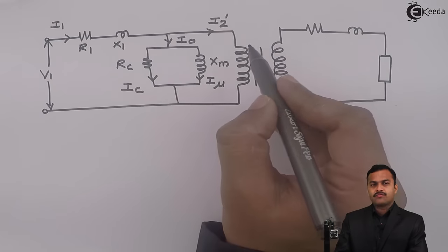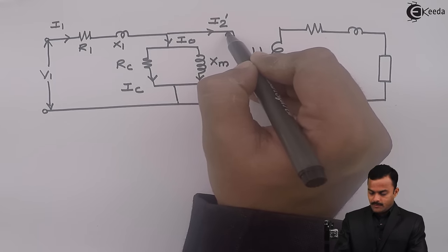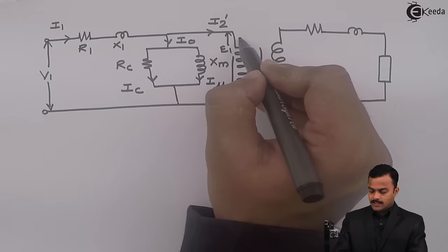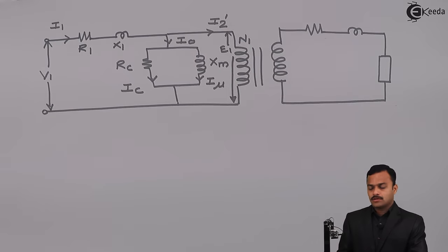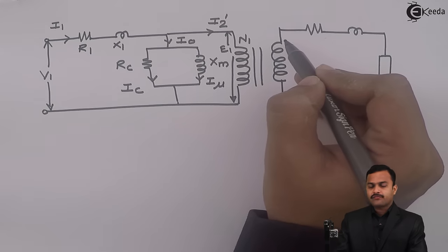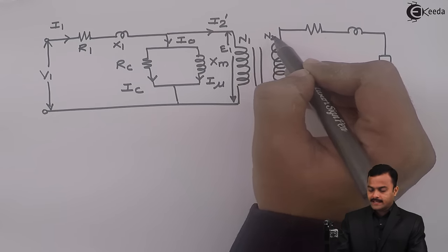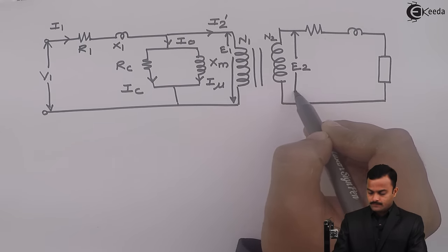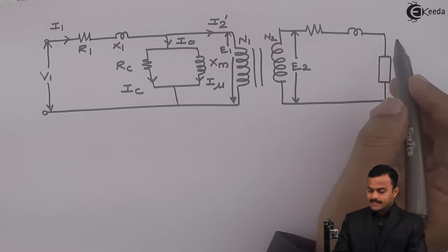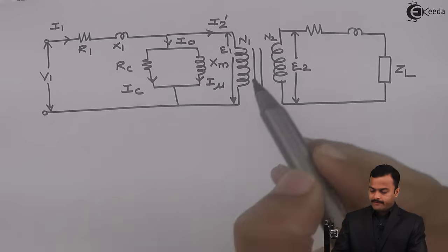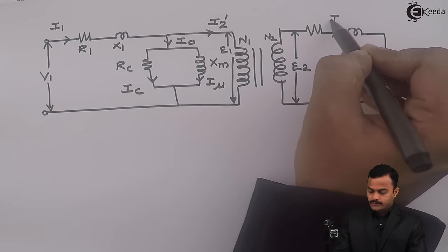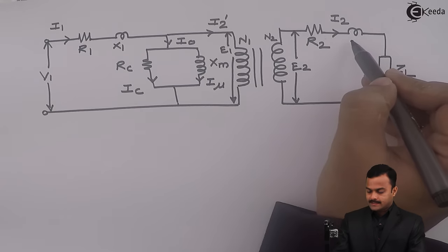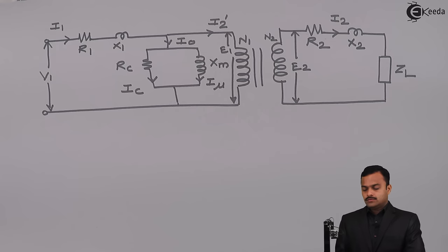Because of flux phi, there will be an EMF induced at the primary side, represented as E1, and that depends upon the number of turns of the primary winding. The same flux phi is linked through secondary turns to give rise to secondary induced EMF E2. If the secondary winding is closed through load ZL, there will be secondary side current I2, which will flow through secondary winding resistance R2 and secondary leakage reactance X2.